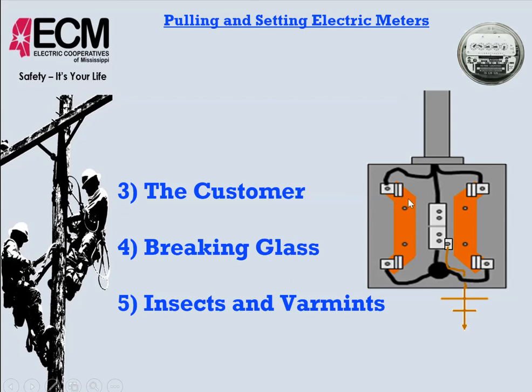One of the things that happens when this takes place is that people want to hit the meter. They line up and set the meter. You always want to put the load side in first, line up the line side, make contact, and then firmly press the meter in there. If there is good meter socket tension on these lugs, it's going to be difficult for us to push it all the way in. Where people make the mistake is taking their hand and hitting the meter to drive it in there, and that's typically where things go wrong.